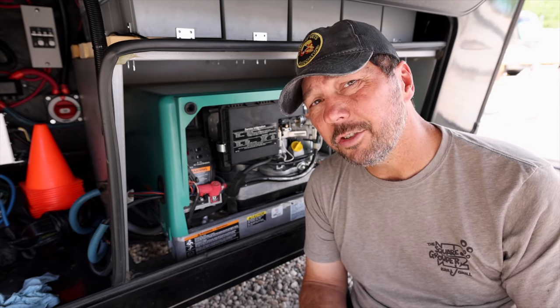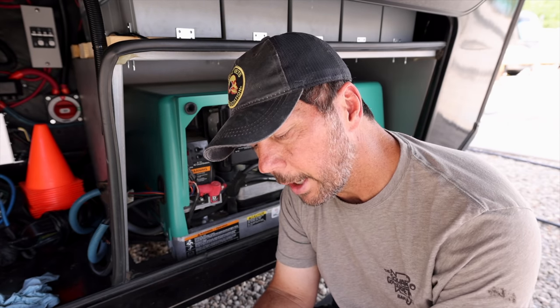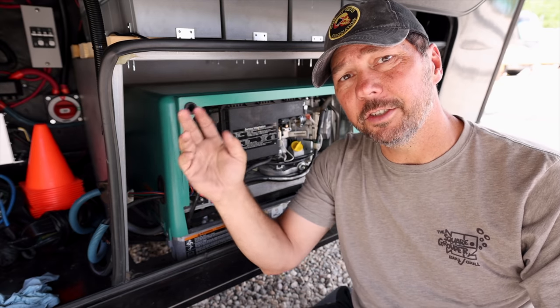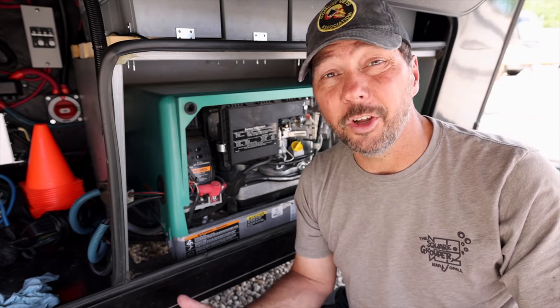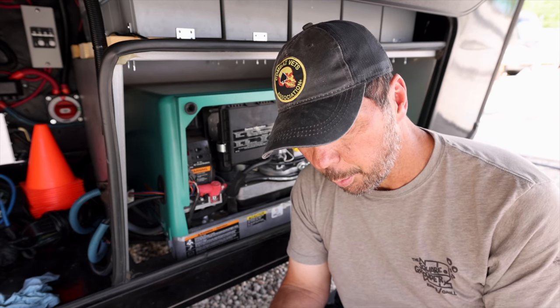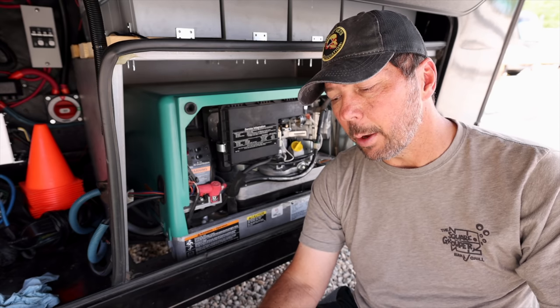However, if I were going to change the fuel filter today, I'd have one snag. This end screws in, so the process is to take your fuel line off, crimp or tap it so fuel's not leaking, run the generator to suck the rest of the fuel through, then unscrew the old filter, screw the new one in, attach your line, and fire it up. The problem I see is that our line is connected with a crimp, meaning once I get it off, I need a new crimp or a worm screw clamp to reconnect it. Don't just go pulling off your fuel line without knowing how you're going to reconnect it.